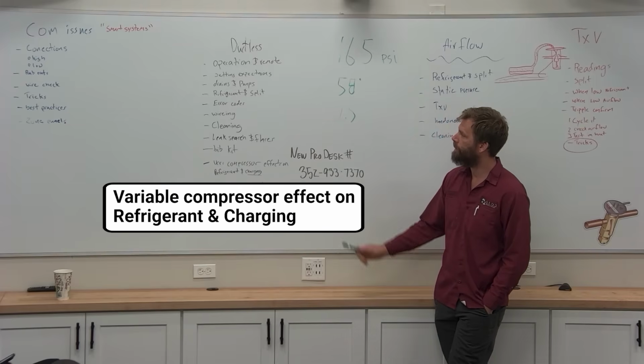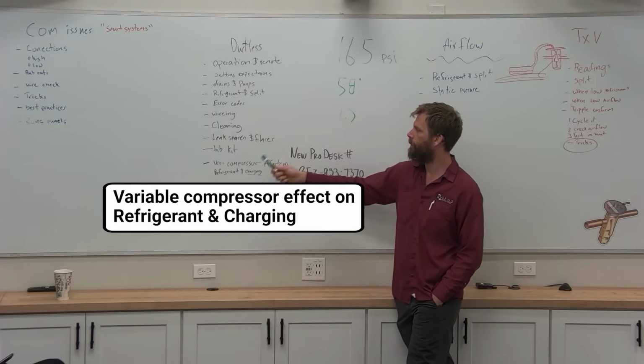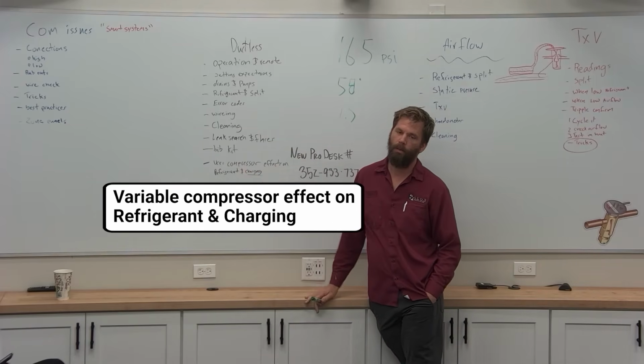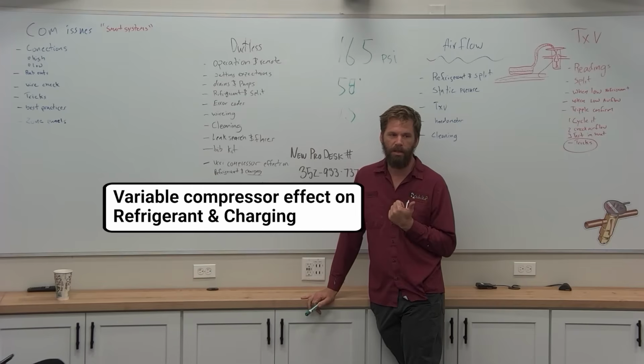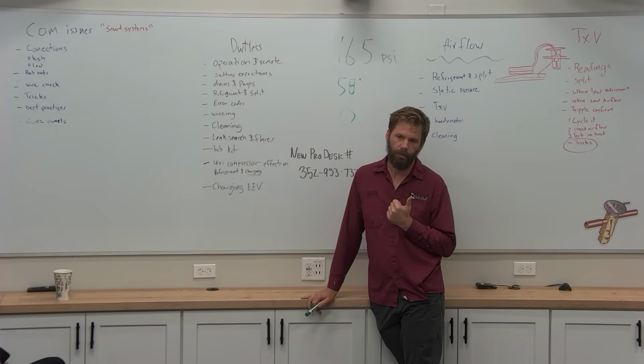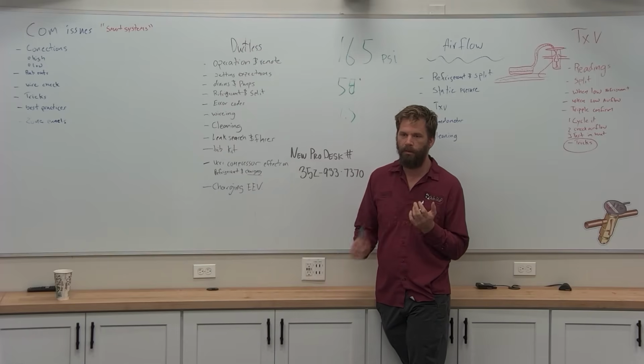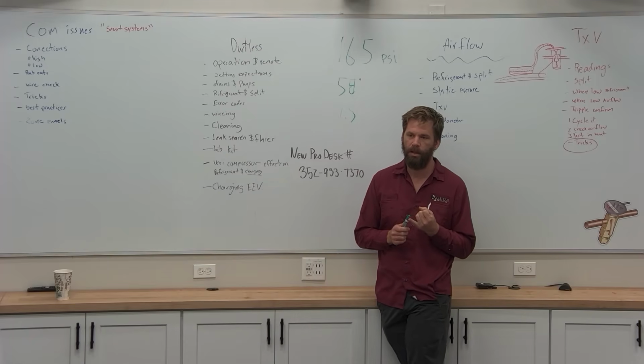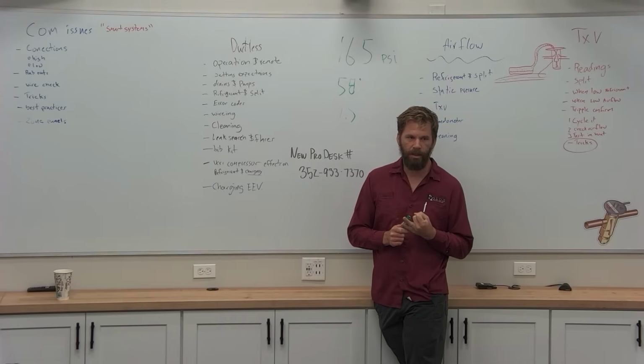So that lesson is all about the fact that we have a variable speed compressor that will adjust based on demand. You need to be running in full speed stage when you're testing this and when you're diagnosing it. And then there's little things that can affect that. You could always drop the temperature down, but it's not running at full speed. Fan speed could be an effect on it. Coil starting to freeze inside. We had one recently where Justin and I were on it. The blower was really nasty.